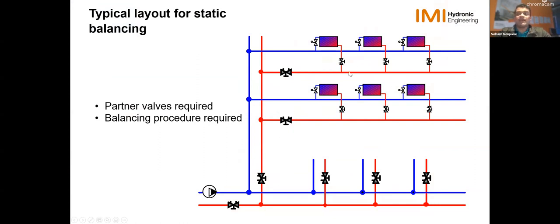So the valves, these manual balancing valves on each terminal, that's pretty standard, known about, right? And partner valves, something we encourage, is very necessary for balancing, because with manual balancing, you have to make sure we balance the system. It's not self-balancing, so we have to make sure proper balancing is done. And partner valves are very important to ensure that we can properly balance, and we'll look into that in more detail later as well. But we want to have partner valves installed on each branch, riser, and closer to the pump. And that's a typical layout you see.